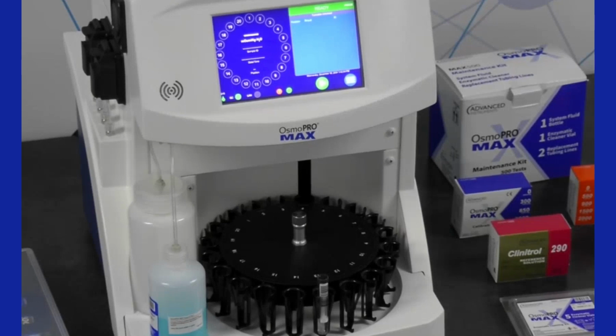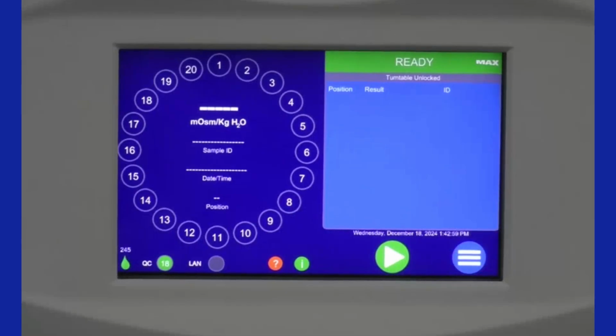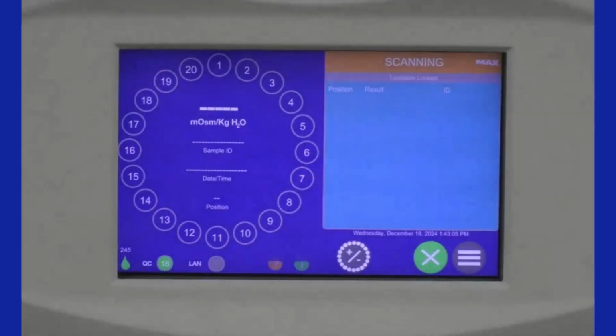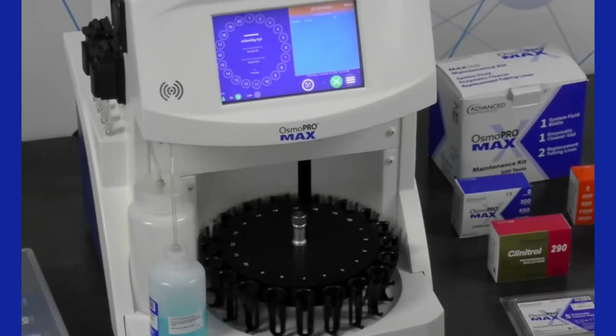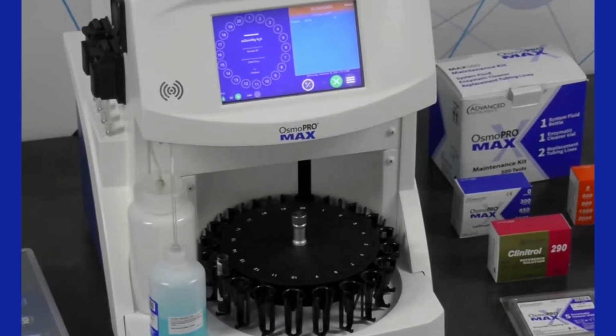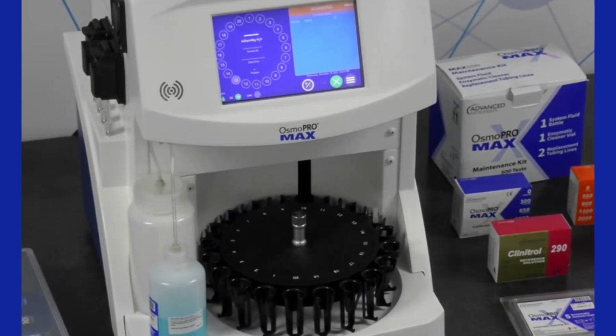So let me go back to the software screen just so you can see what the play button looks like. So yeah, once you've loaded your sample, you just hit this play button. That's exactly what it looks like. And then you can see the turntable will home itself on position 20, and then it will count down from position 20. Doesn't matter where you put your sample tubes. It will go looking for it. It'll check every position and scan each one where it finds a barcode and a patient identifier.